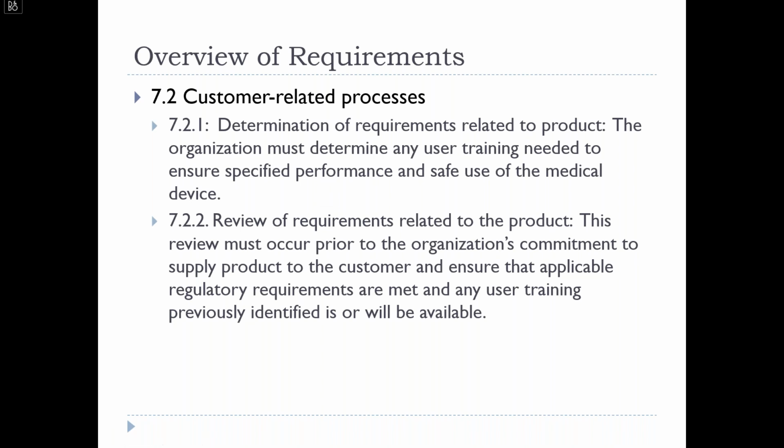7.2.1, a very uniquely 13485 requirement. The organization needs to determine any user training needed to ensure the performance and safe use of the medical device. I know, for example, I just administered an at-home COVID test to a member of my household. That at-home COVID test had instructions to ensure the performance of that medical device.